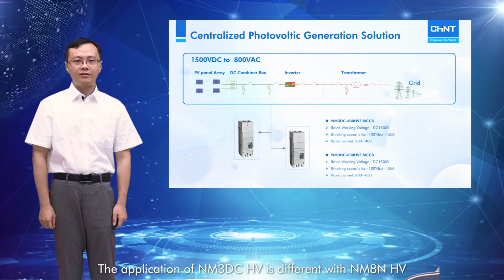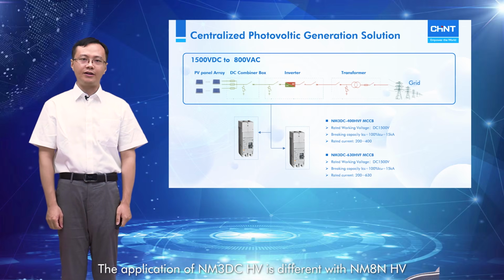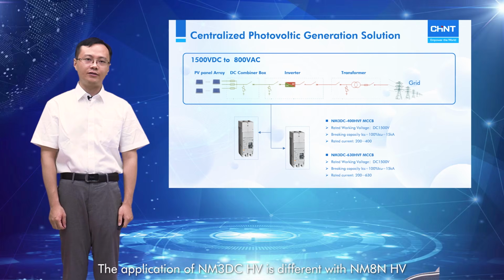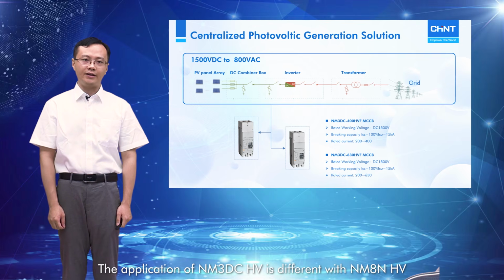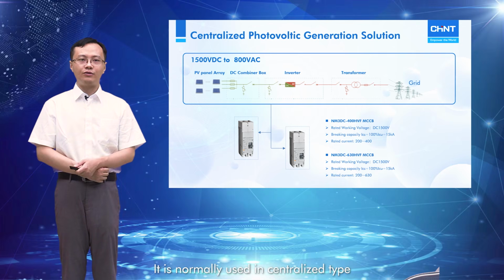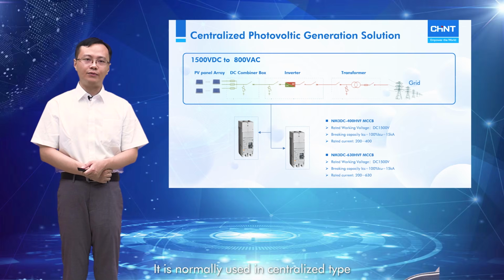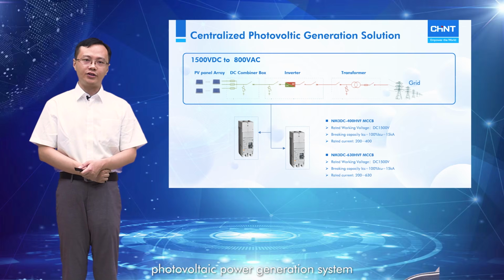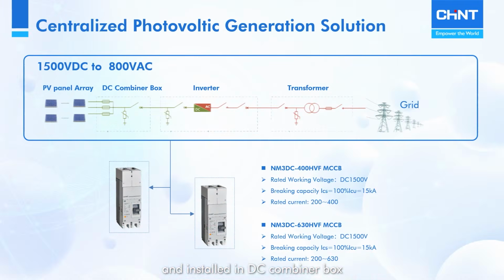The application of NM3DC HV is a little different from NM8N HV. It is normally used in a centralized type photovoltaic power generation system, and it is installed in the DC combiner box.